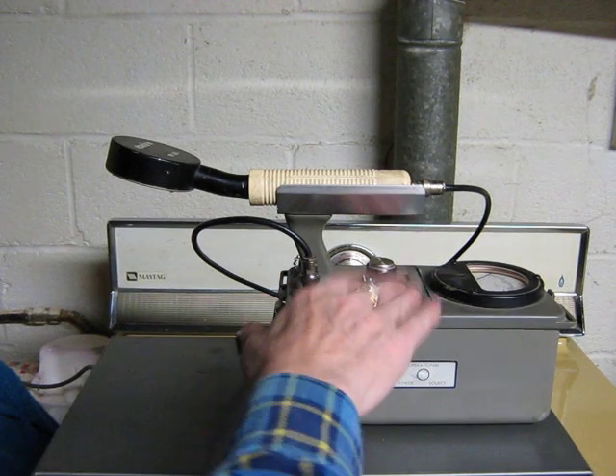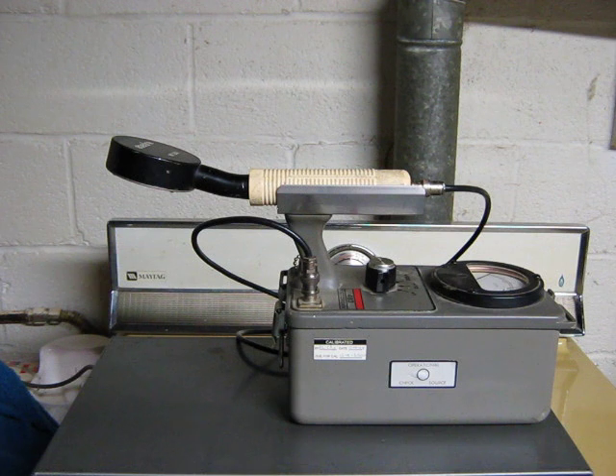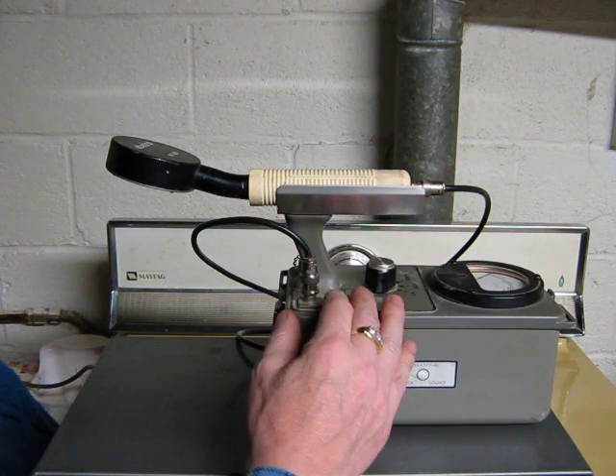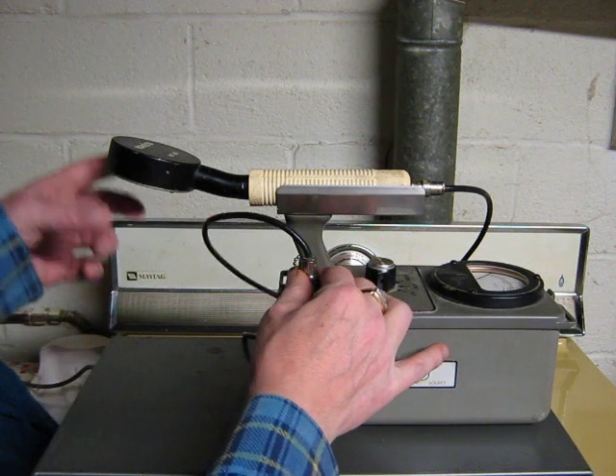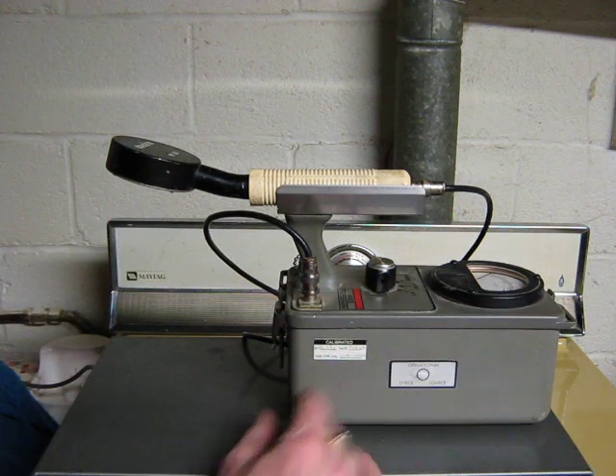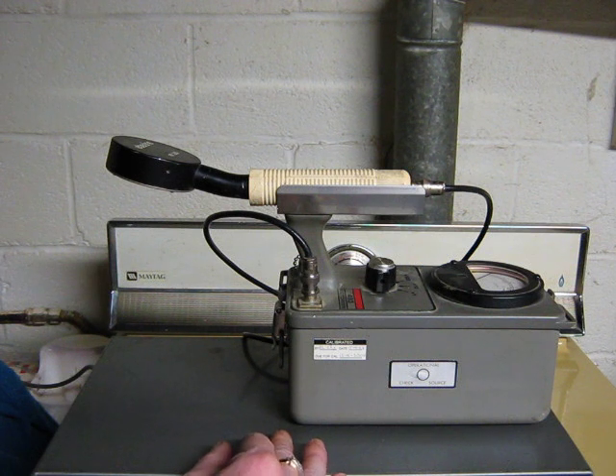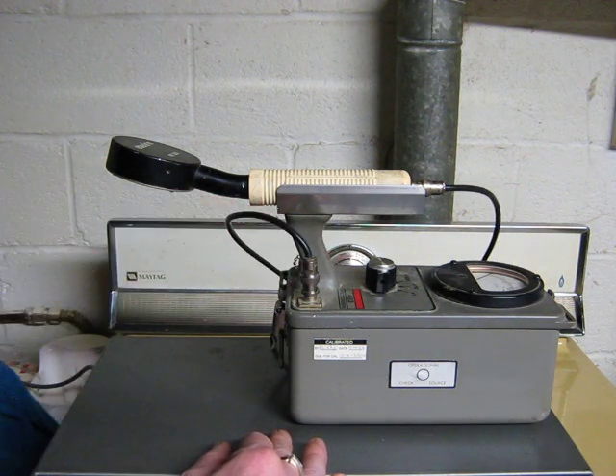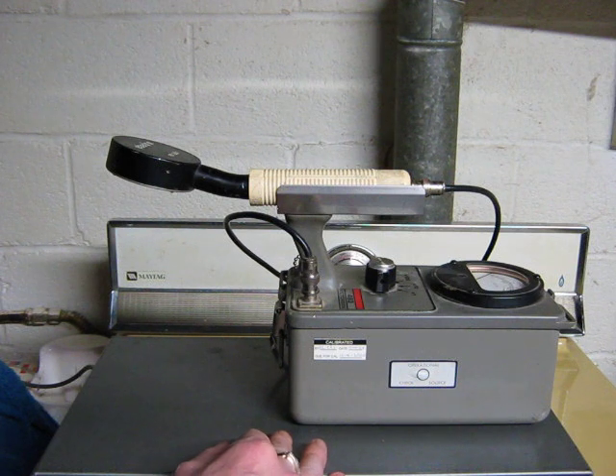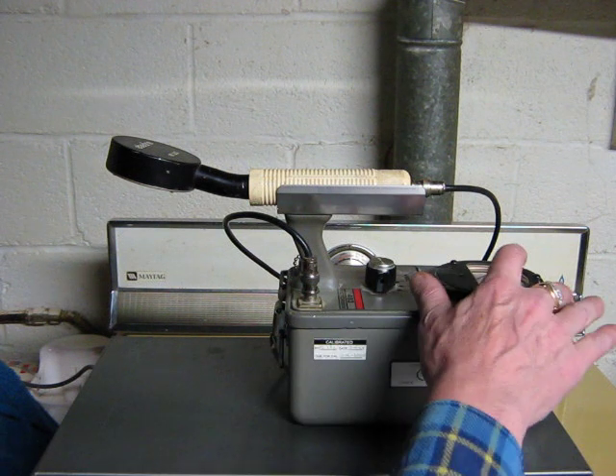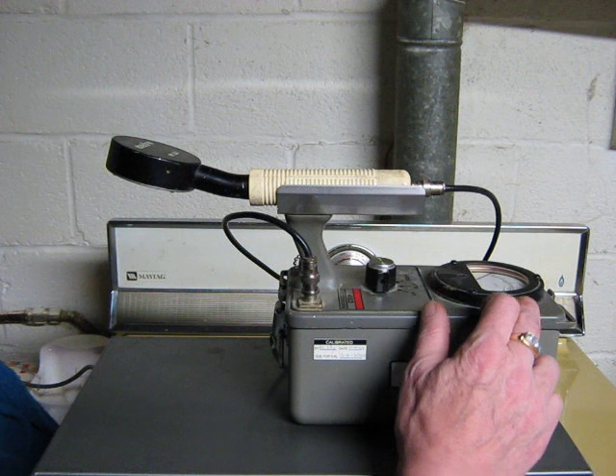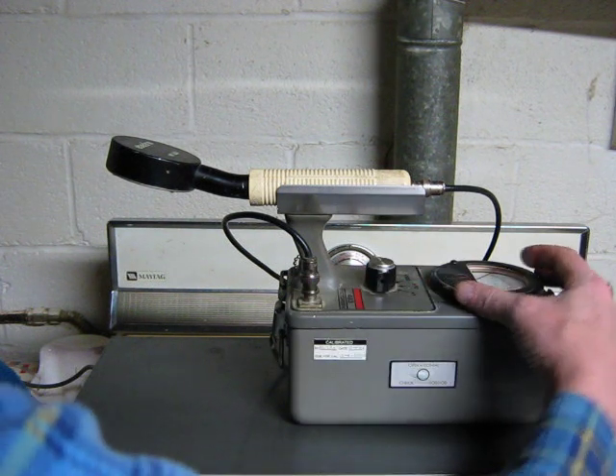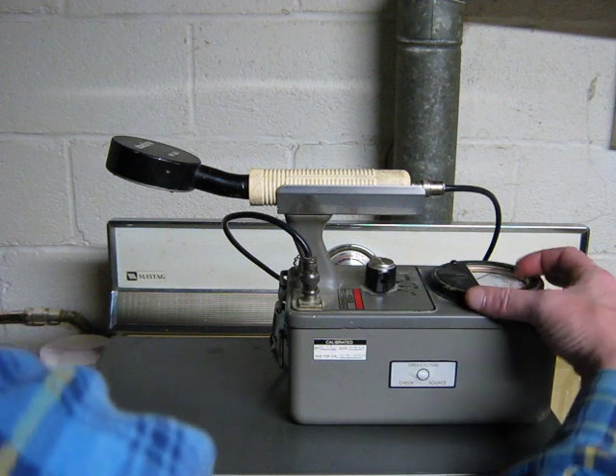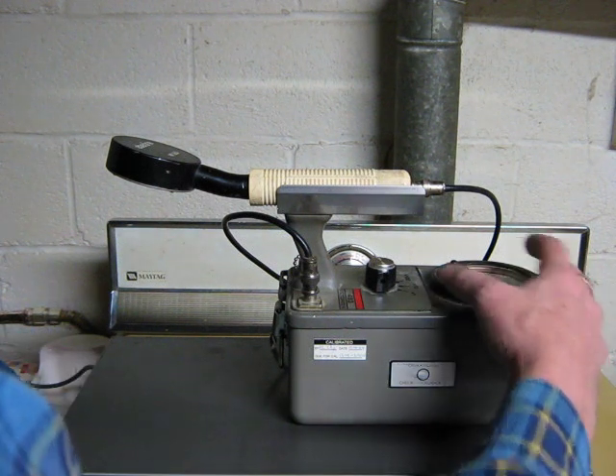Okay, this is a radiological survey meter. Most of us know it as a Geiger counter. It has a probe, a bit of electronics in here, a couple of batteries. It is a device, as many of you know, used to give an account of how much radiation is present, what is the dose rate. Now, this meter, it's an analog meter, old school, calibrated in counts per minute and millirems per hour. We're only going to be dealing with counts per minute here, and we'll get to why that is later.